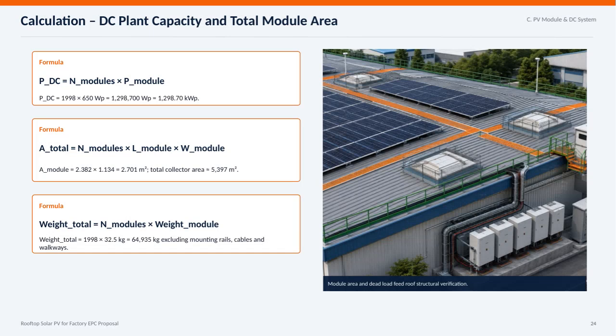Here we calculate the DC plant capacity and the total module area for our rooftop solar PV system. Starting with the DC capacity, we multiply the number of modules by the power rating per module. Here, with 1,998 modules, each rated at 650 watts peak, we get a total DC capacity of approximately 1,298.7 kilowatts peak.